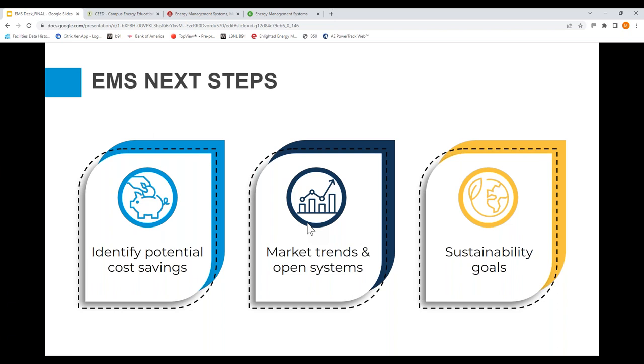Where the analytics software would take all of that data, do its analysis, and then spit something out and say, yesterday there were 3 hours during the day that you should have been using your economizer and taking advantage of free cooling and you were not. And so that's the advantage there: it does that analysis for you, and it does it all the time. It's constantly looking at that kind of stuff and making those analyses for you. So that software comes prepackaged with a lot of these analytics in it. So at the end of the day, I would say, yes, it is an EMS. As long as it's bringing in energy data, it definitely fits that category.